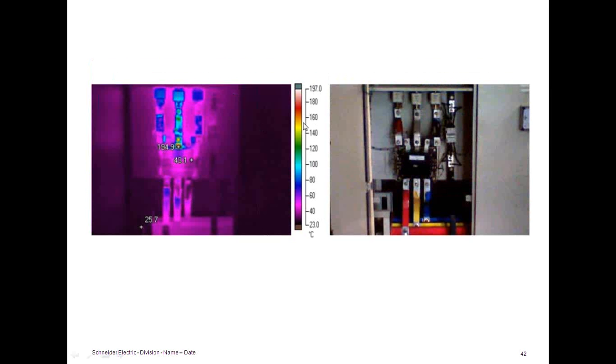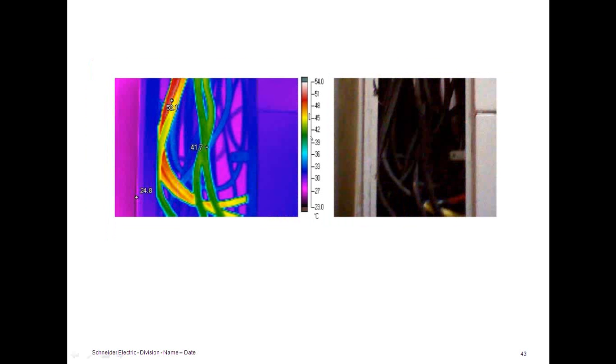This is a cable from the same UPS, but the output of the UPS is going to all the computer nodes in the building. What you can see are five cables here, 3 in green, 2 in red. The 3 in green are the line 1, 2, and 3 line conductors, and the 2 red are neutral conductors. The customer used a double neutral because the neutral was carrying a huge current because of zero sequence harmonics.